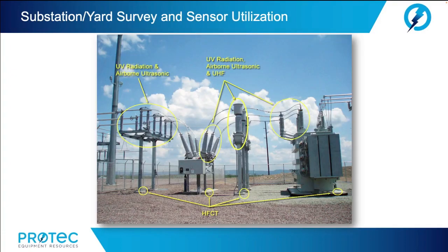For substation yards, we can use a variety of sensors. We can use corona cameras for detection of the UV radiation. We can also use the airborne ultrasonic techniques and the parabolic dishes. Along the ground straps, we can also use the high-frequency CTs and the ultra-high frequency sensors.